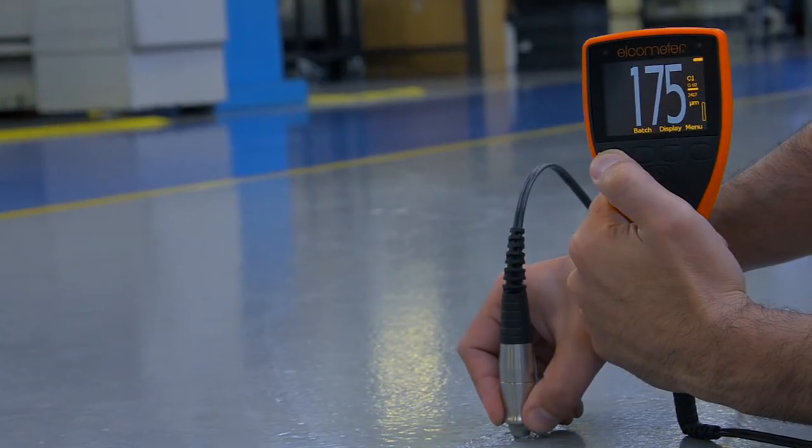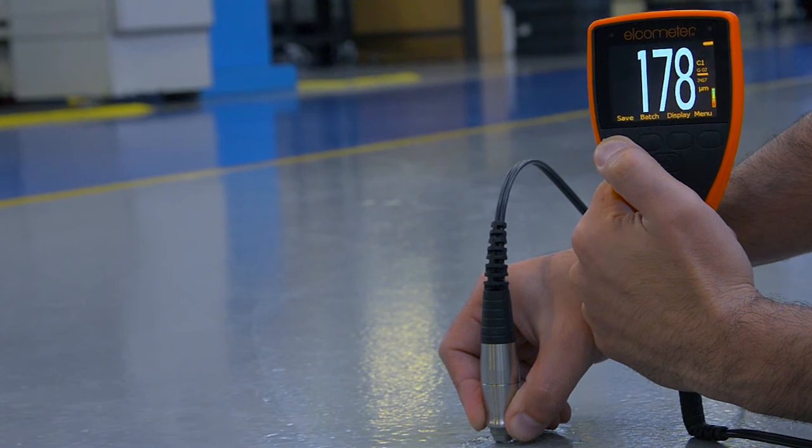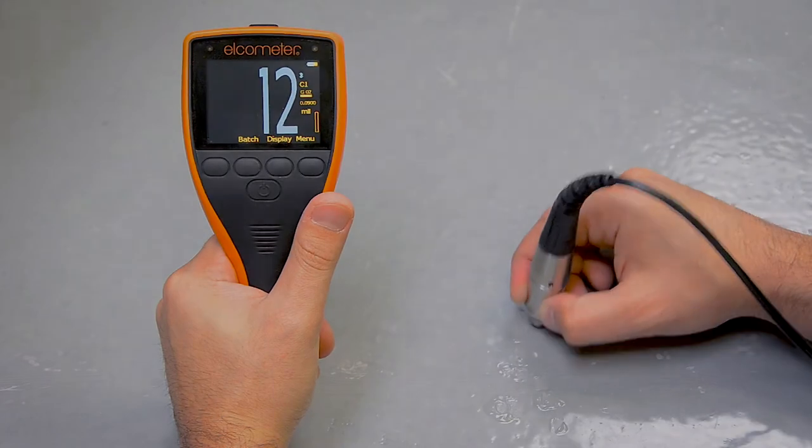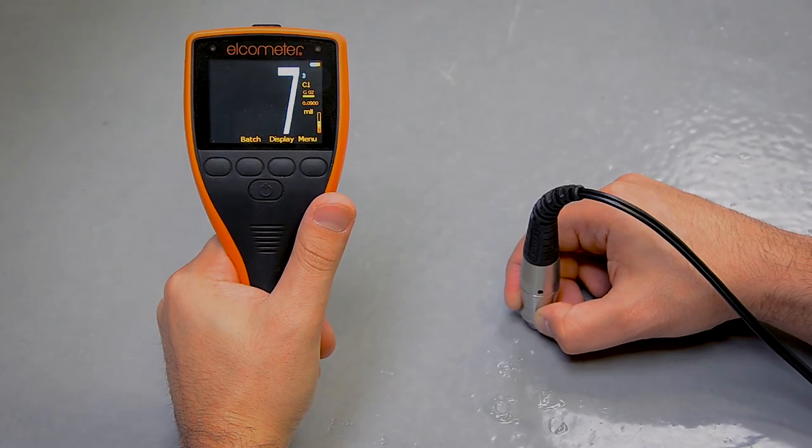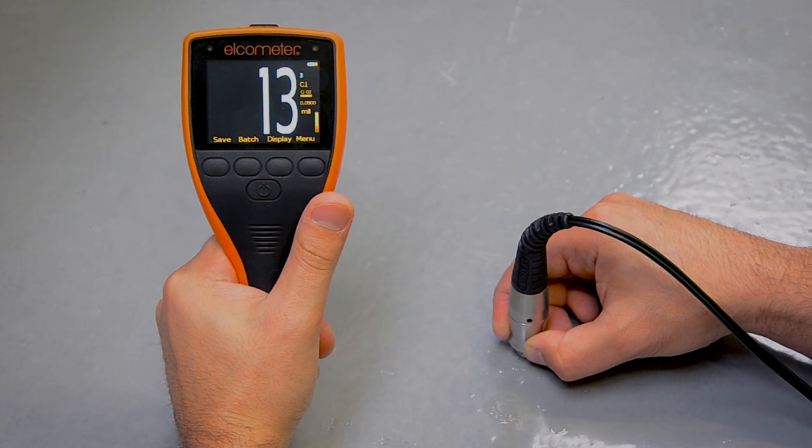As a result you may have to move the probe around to obtain a reading, ensuring you have an adequate amount of ultrasonic couplant on the surface wherever you're placing the probe. This is perfectly normal when using an ultrasonic gauge or when measuring coatings on concrete or other similar substrates.